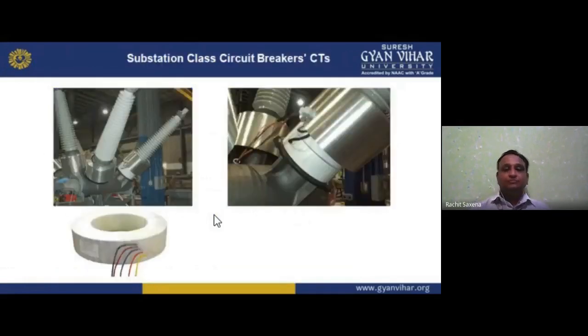Now, these are substation class circuit breakers. See, these are circuit breakers and CTs, current transformers. We have substation class circuit breakers, SF6 and so many others. We have air blast, SF6 and vacuum. SF6 is the gas circuit breaker. We have the oil circuit breaker, the air blast circuit breaker, and the vacuum circuit breaker.